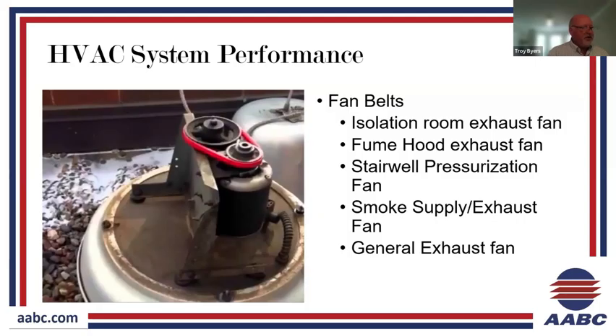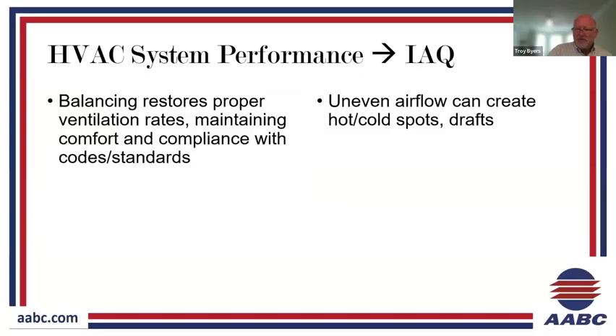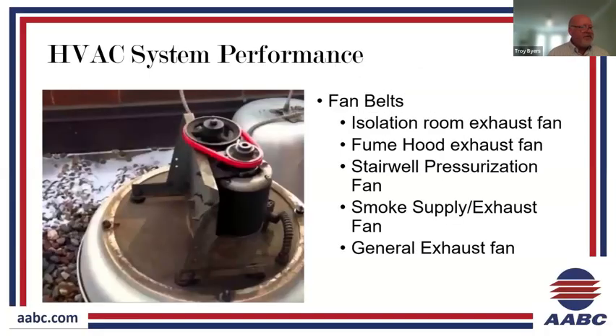The stairwell pressurization fans, we talked about, annual testing is sometimes required there. But if it's not being performed, there's a good chance that you've got a lack of maintenance and checks on those fans, where, again, your belts could be degraded or cracked or even broken. And one thing to point out about our stairwell pressurization fans when it comes to belts is that they're required to have 1.5 times the number of belts for its given rated horsepower. So that minimizes the chances of not having any belt to perform. But it just, I guess, highlights the criticality of belts when it comes to these fan systems.